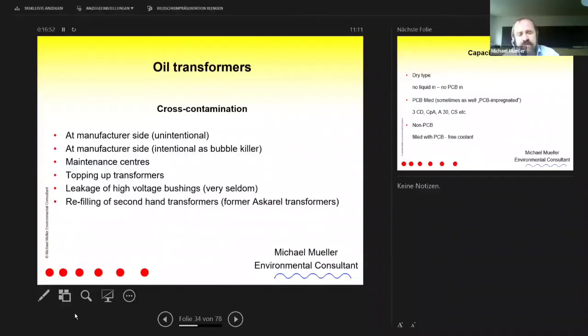That is only in transformers of maybe 200 MVA or 400 MVA like that. They have huge bushings, like 5 meters long, and inside the bushing there's a coolant as well, an encapsulated coolant that is Askarel, and sometimes after a certain time they start leaking and it drops into the transformer. And of course, that is something that could also be a case in Palestine.